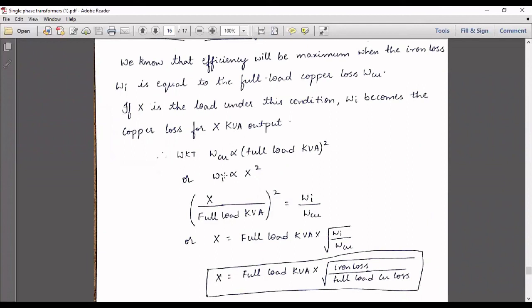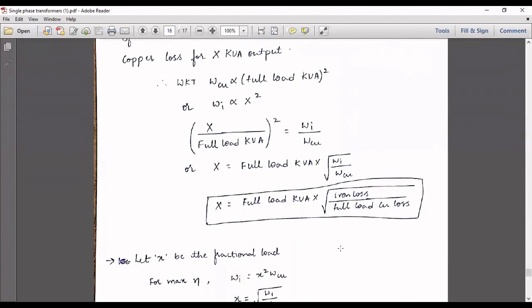But we know that Wi is equal to WCU. So Wi can also be expressed as proportional to X square, where capital X is the load considered. If I take the ratio of these two, Wi by WCU, it will be X divided by full load kVA whole square, or capital X will be equal to full load kVA into square root of Wi by WCU. So the load kVA rating corresponding to maximum efficiency, capital X, is given by full load kVA into square root of iron loss by full load copper loss. This is the equation to find the load, that is the kVA rating, at maximum efficiency condition.